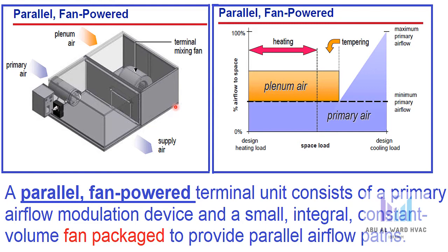When the space cooling load drops below the minimum primary airflow setting, the small fan activates to mix warm plenum air with the cool primary air. This increases the total airflow to the space and creates a warmer supply air condition. If additional heating is required with the terminal fan on, a heating coil can be used to further warm the supply air. Operating the fan is a form of energy recovery — it tempers the supply air with heat from the building and lights carried by the return air rather than with new energy, thus delaying the start of the heating coil. When in cooling mode, the supply airflow to the space equals the primary airflow. When in tempering and heating modes, the space receives a constant supply airflow equal to the minimum primary airflow plus the airflow delivered by the terminal fan. Usually the primary airflow is not allowed to shut off completely because of the space requirements for ventilation air.